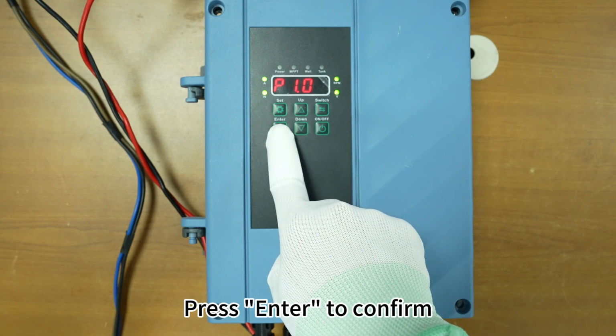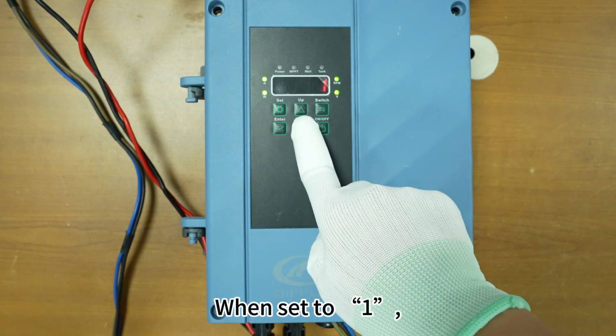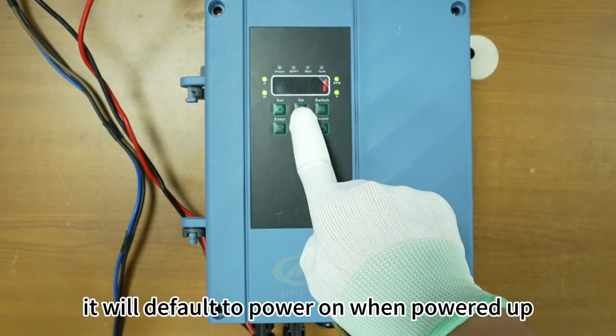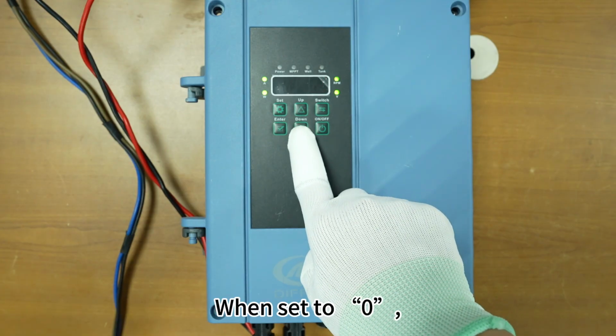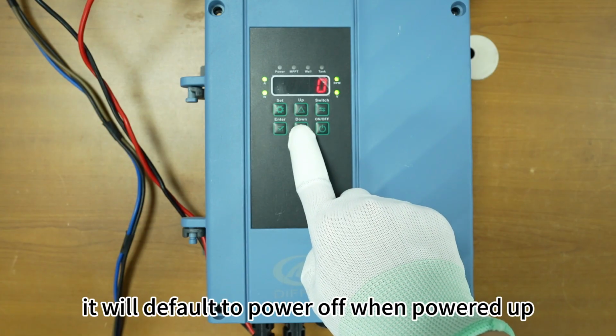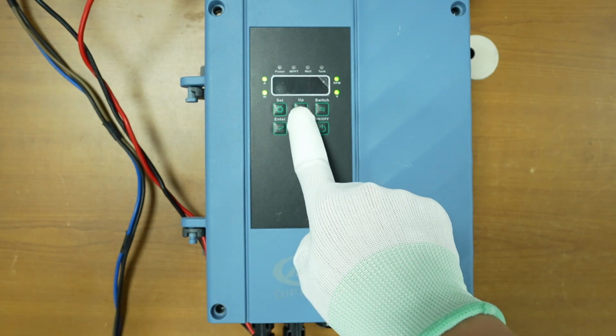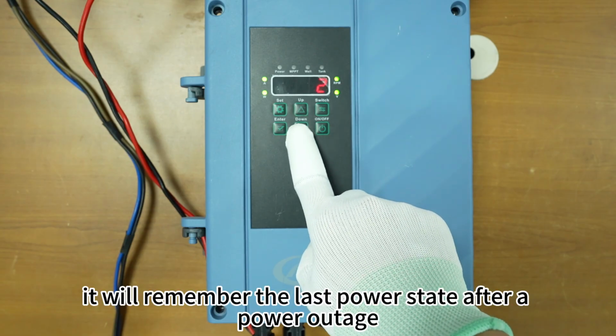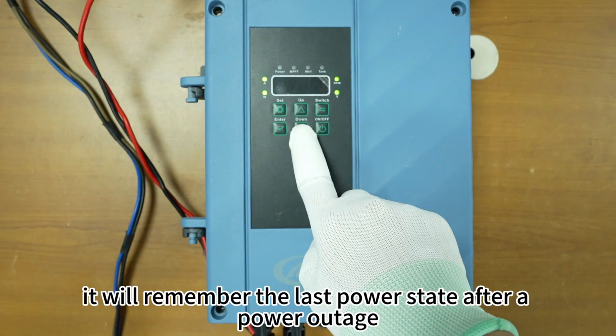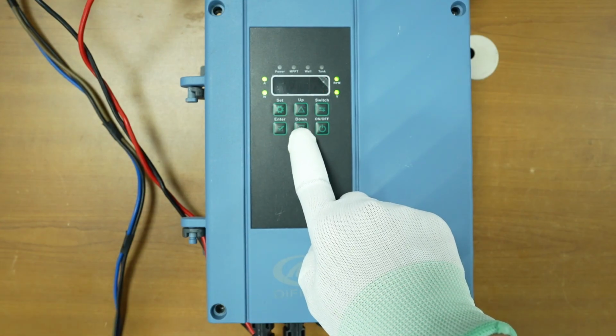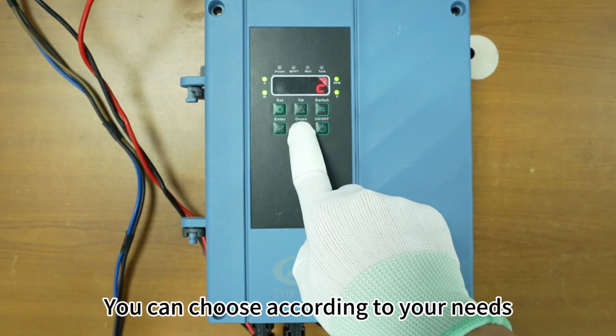Press Enter to confirm. When set to 1, it will default to power on when powered up. When set to 0, it will default to power off when powered up. When set to 2, it will remember the last power state after a power outage. You can choose according to your needs.